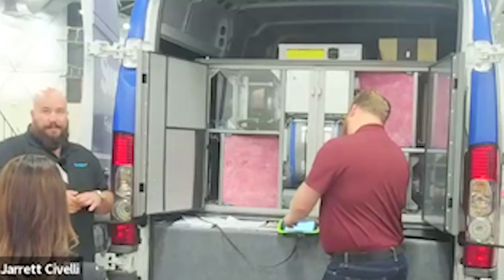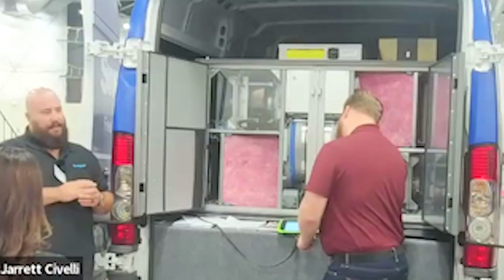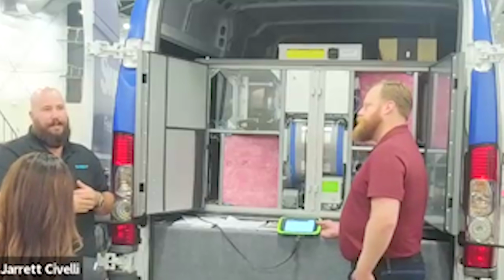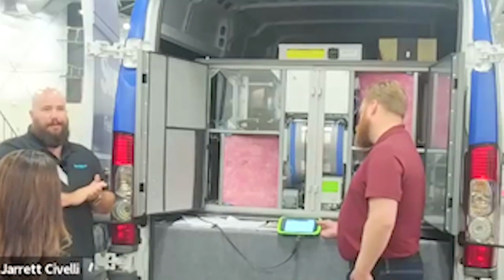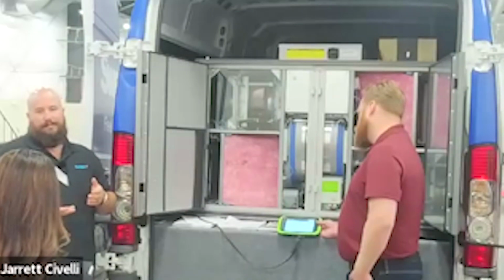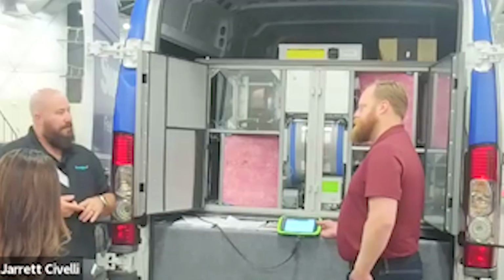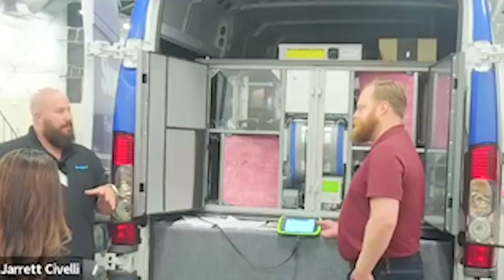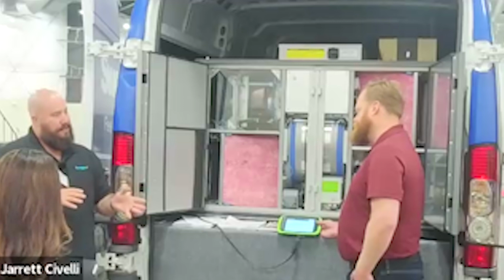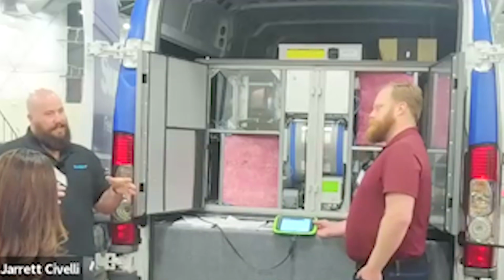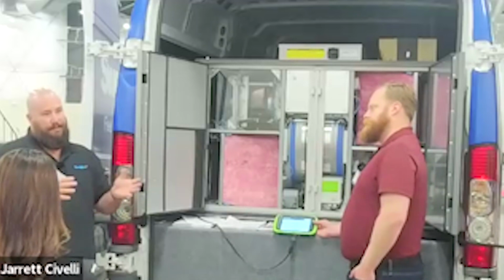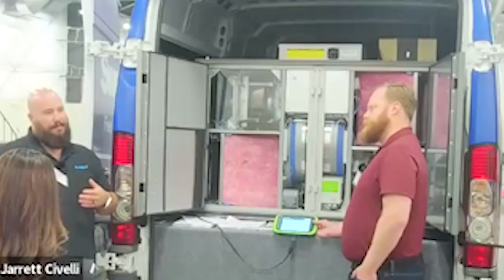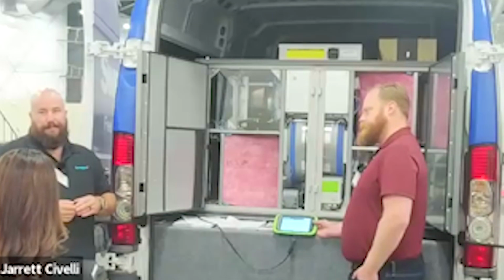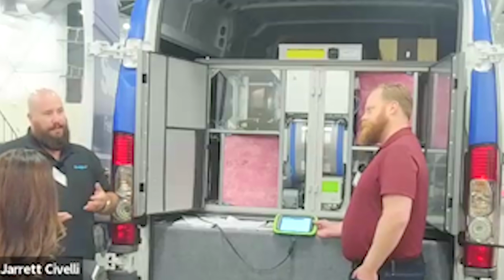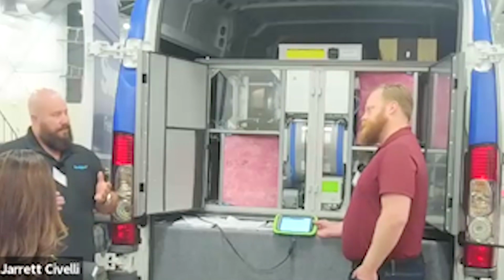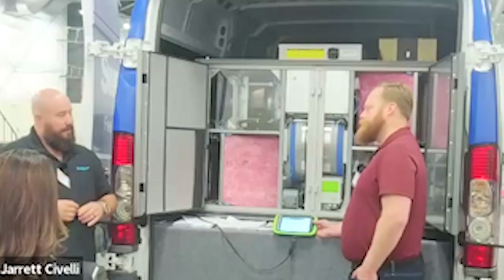You can set it up for medium static. If you needed a duct pressure sensor two-thirds of the way down the duct, they make a factory sensor for that, so we can maintain higher static, like 1.5 to 2.5 inches of water column. That's becoming a little less common because we want to try to decouple our incoming air from our fan coils to save energy. At least in Washington, that's a big part of the energy code: decoupling your DOAS system from your fan coil systems so you're just heating the replacement air and dropping it into the space, rather than running the fan coil to push that air back into the space. That reduces your fan load. You don't have to have an extra fan running. The local space zone will only turn the fan on and heat or cool the space when needed, which reduces your energy footprint.